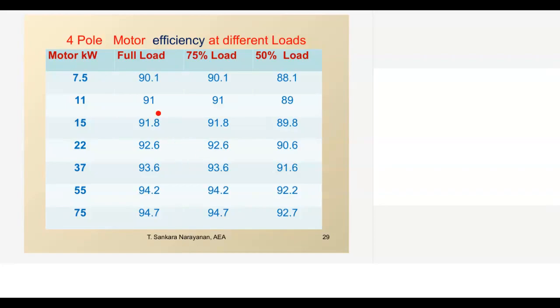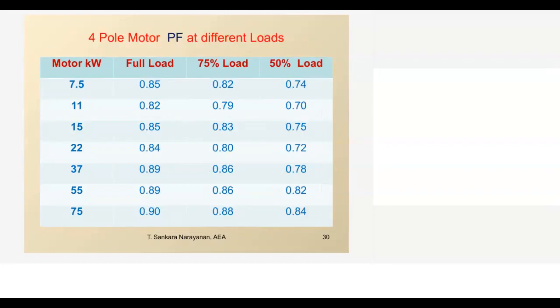Okay. See, normally the motor power factor will change as per the load. At lower load, the power factor will be very low. When the load increases, it can come up to the design power factor. So this is what is shown here. The motor is designed for 0.85 PF. At 75% load, it is 0.82. When the motor is at 50% load, the PF drops to 0.74. If it is 30% load, this can go down to 0.5 also.